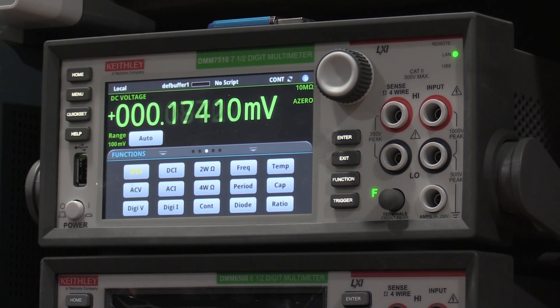As the meter is new it's a good idea to have calibrations be very frequent as the components age and kind of settle down. You can extend the calibration interval to something longer — I'll probably push it out to a year and a half, maybe two years. But the problem is you have to keep track of everything. If I did an alignment for someone based on the accuracy of my 7510 and my calibration cycle was say five years, and six months after getting it calibrated I send it out and it comes back bad — one of the ranges is out — everything I've done in that five-year period is suspect. It's not confirmed.